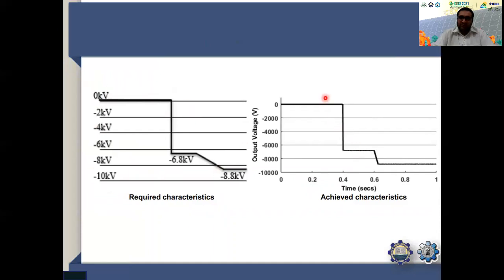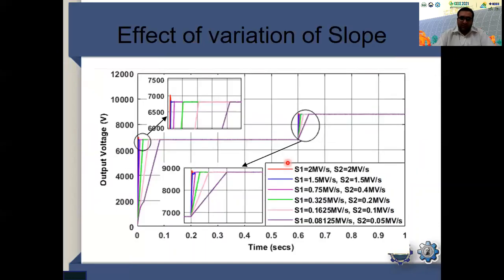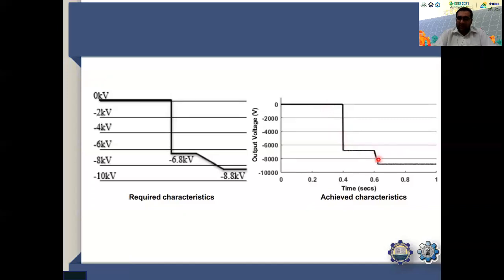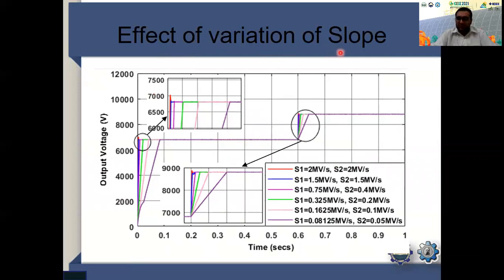So these were our required characteristics, and these are the achieved characteristics by implementing the PI control. Not only have we now obtained the output voltage levels of 6.8 kilovolt and 8.8 kilovolt, but we have also achieved that particular transient response. Here is the effect of variation of the slope of this waveform. If we keep on increasing the slope, the rise time of this waveform decreases, but if it is increased beyond a certain value, some overshoots start to appear in the output again. So based on this simulation graph, we will select a value where the rise time is also minimum and there are no overshoots in the output.